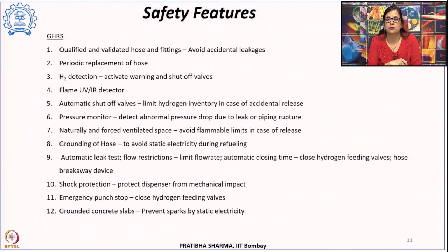Pressure monitors are present so as to detect any abnormal pressure drop which could arise because of a leak or piping rupture. And these spaces are either naturally ventilated or forced ventilated so as to avoid any flammable conditions in case of a release. These hoses are grounded so as to avoid static electricity which could be generated during the refueling. And then automatic leak testing and flow restrictions are included, with automatic closing times so as to not only limit the flow rate but also close the feeding valves, and hose breakaway devices are present. Then there is shock protection to protect the dispenser from mechanical impact, and emergency push stops so as to close the hydrogen feeding valves. Then these slabs are grounded so as to avoid any sparks by static electricity.